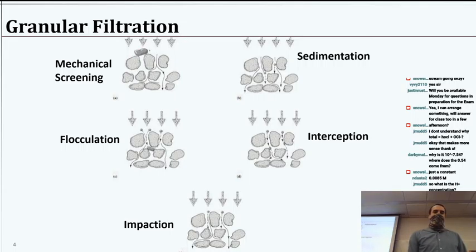Sometimes it can do some mechanical screening, like we were just talking about for the membranes, but that's not the majority of it. So if you have a large particle too large to make it through the pores, yeah, it'll do some of that, especially as the pores get clogged with more and more smaller particles. It'll start constricting the pores, and then maybe we get more size exclusion. But we don't want to rely on that.